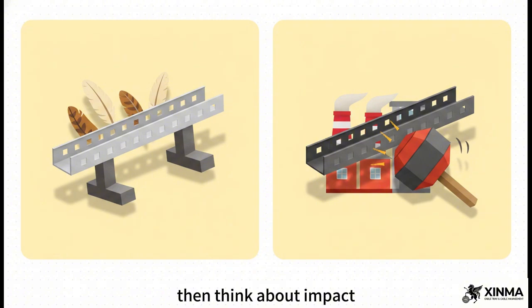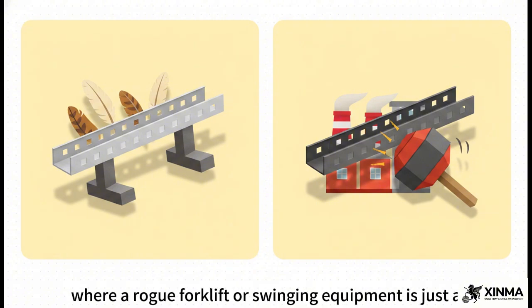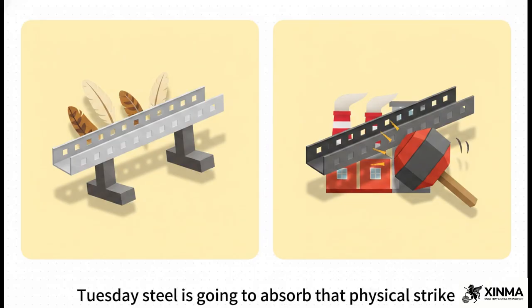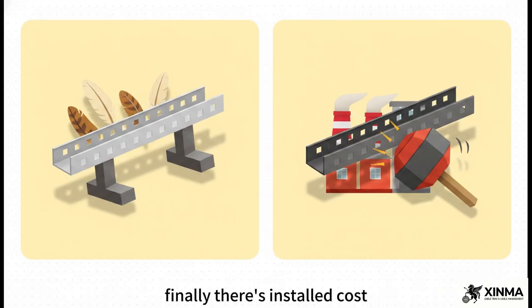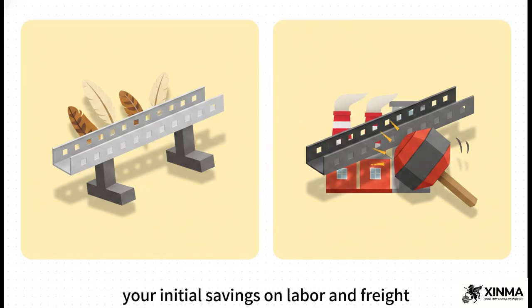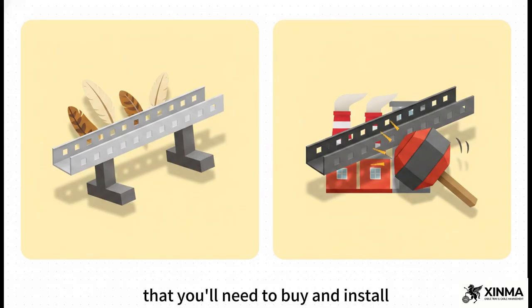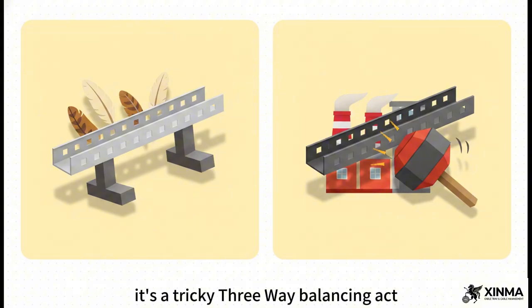Then think about impact. If you're in a heavy industrial plant where a rogue forklift or swinging equipment is just a Tuesday, steel is going to absorb that physical strike way better than aluminum. Finally, there's installed cost. You've got to carefully balance your initial savings on labor and freight against the very real possibility that you'll need to buy and install more frequent support brackets. It's a tricky three-way balancing act.